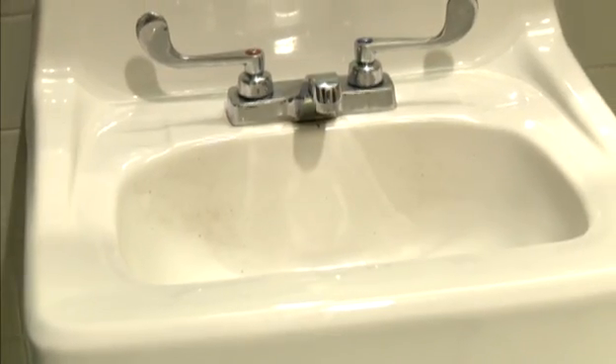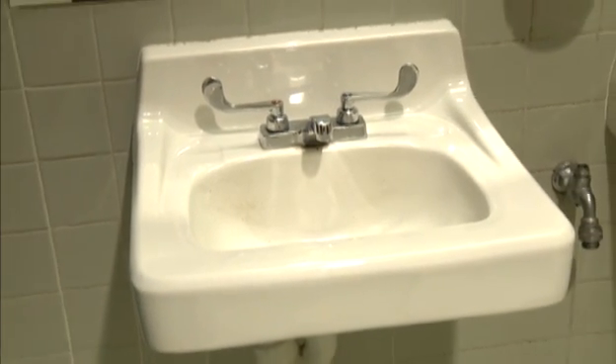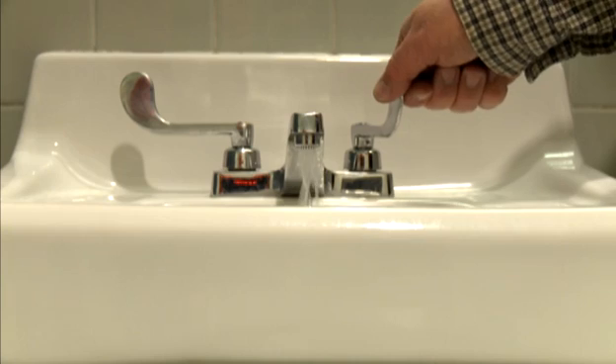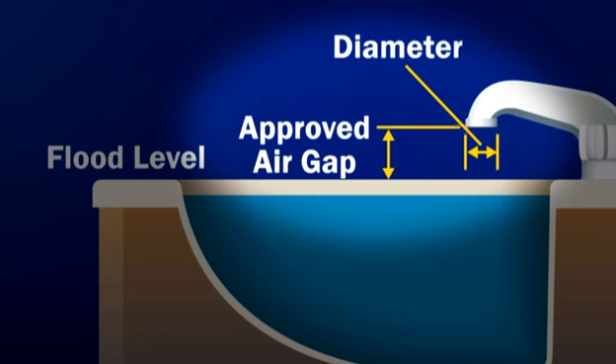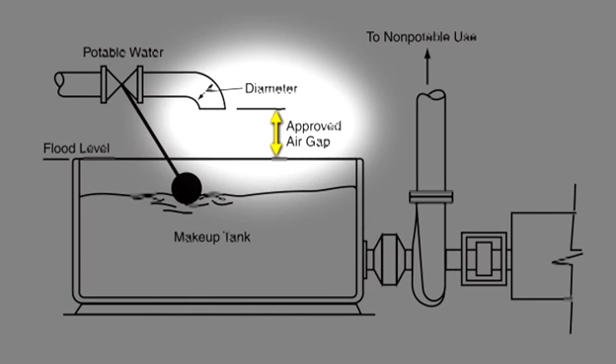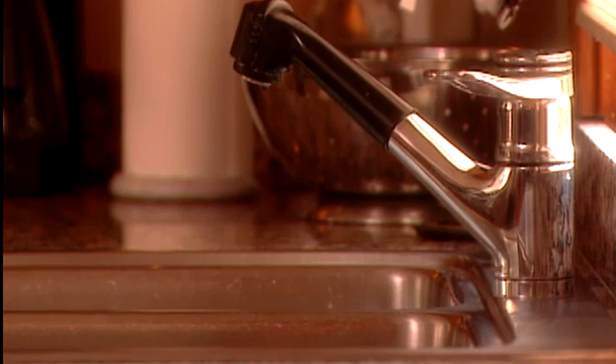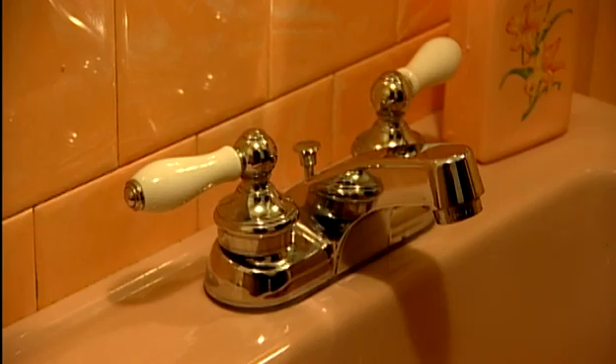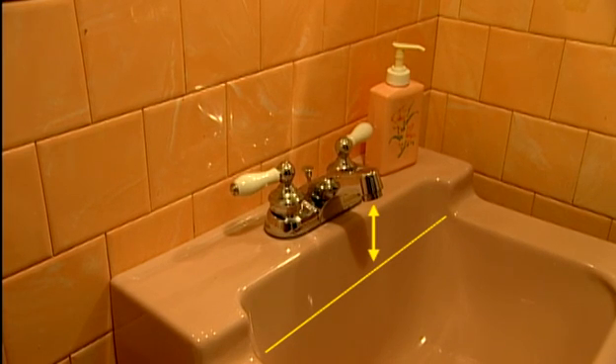Air gap is the most effective way to prevent a cross-connection by providing a separation between a potable water source and a non-potable source, because air disrupts the flow. An air gap is not a device — rather, it is simply physical space. The most common place you see an air gap is in a kitchen and bathroom. There should always be space between the water source and the flood level rim of the receiving vessel.